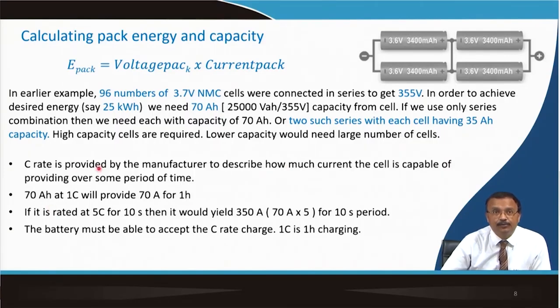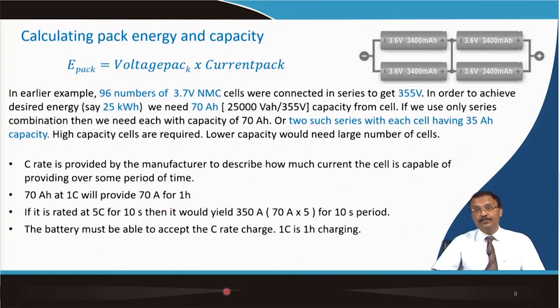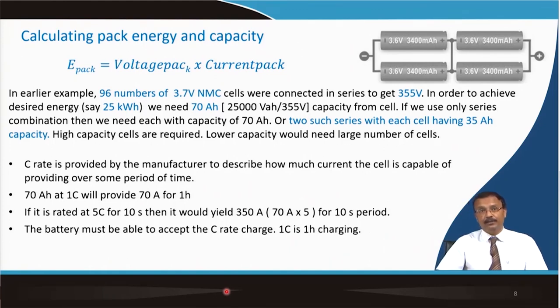The C-rate is specified by the manufacturer, who will tell you the C-rate required for charging and discharging. You cannot increase the C-rate indefinitely or your battery will be dead. A 70 Ah cell at 1C provides 70 amperes for 1 hour. If rated 5C for 10 seconds, it would yield 350 amperes (70 Ah × 5) for that 10-second period.